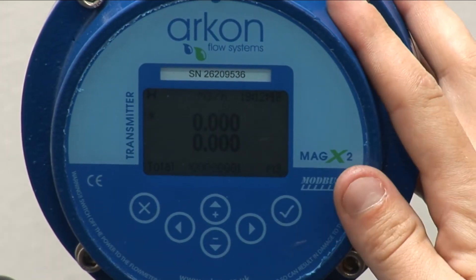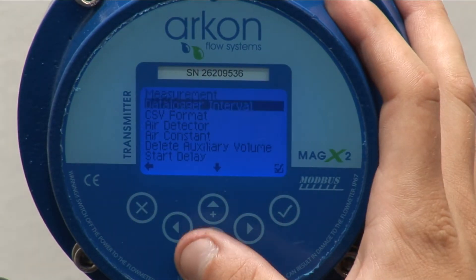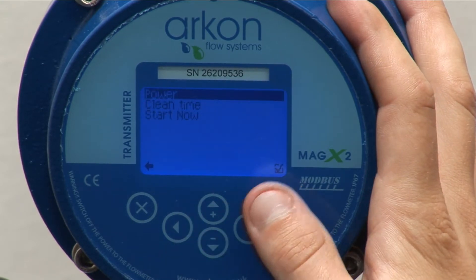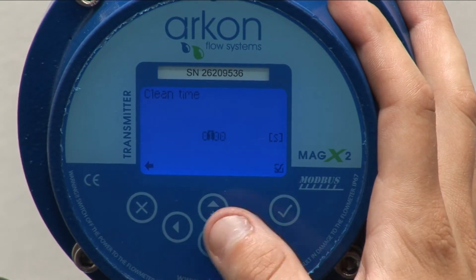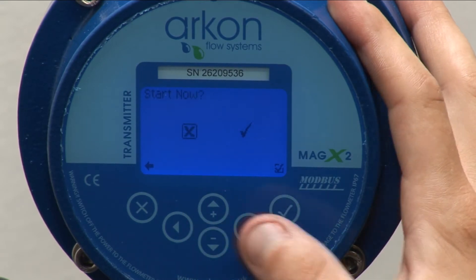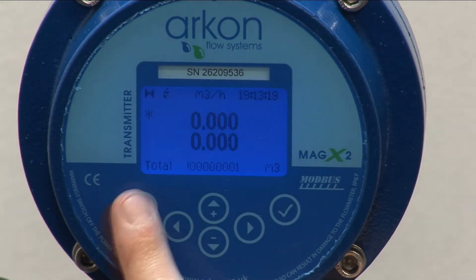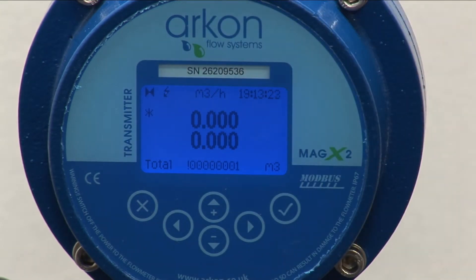Number 5: Execute the electrode cleaning procedure for 10 seconds. Make sure the measured medium is flowing in the pipes and turn on the electrode cleaning for 10 seconds. A lightning symbol is shown on the display; the meter does not show the flow value during cleaning. Please note, electrode cleaning is valid only for MAGX2 and MAGX1.